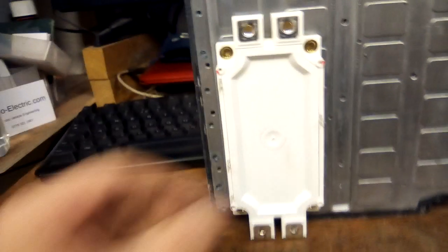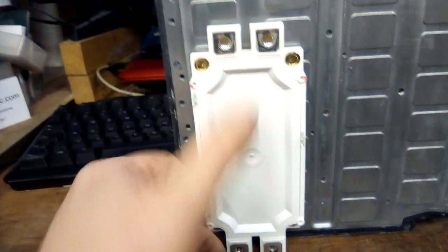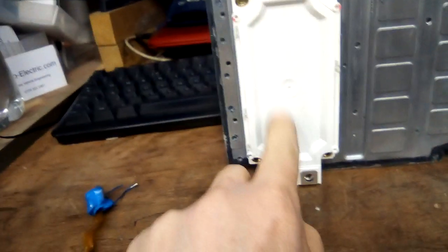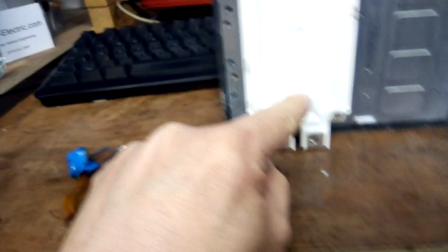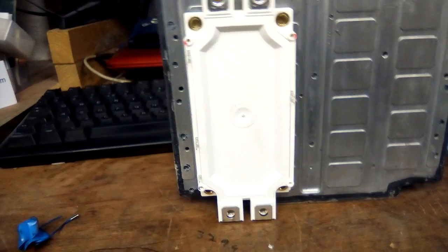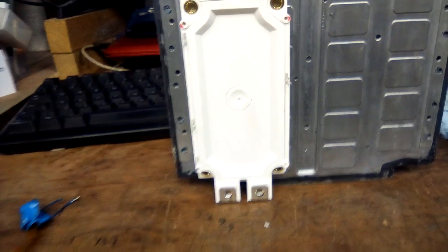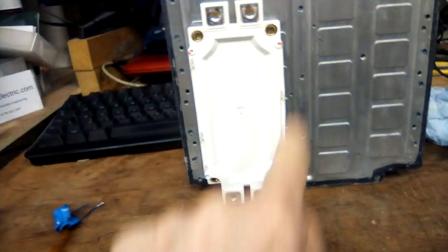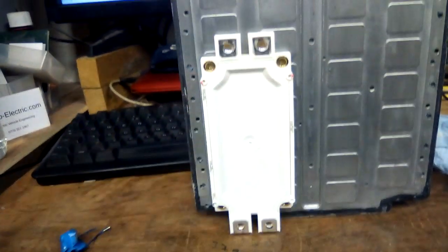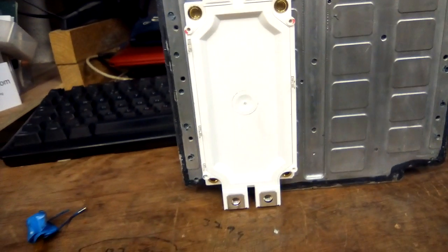Inside there is six IGBTs. They're all sharing the same die, so you got like three on this side and three on that side, plus the freewheeling diodes are on the die. Each of those IGBTs can actually handle 200 amps and they go in parallel to 600. They're laid out in a way with channels around them so that you don't get the voltage arc across.